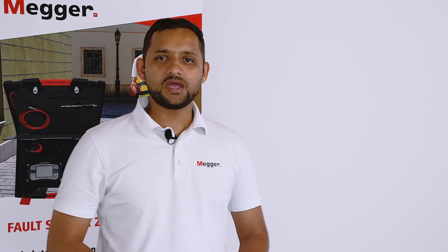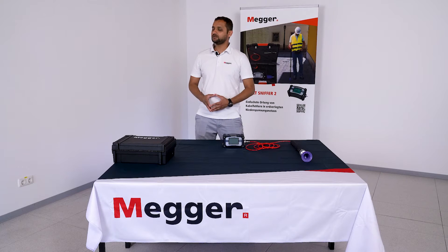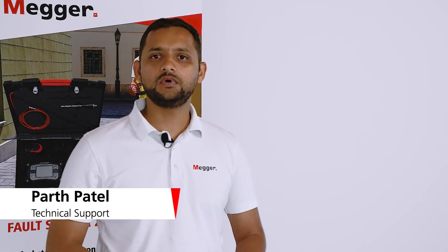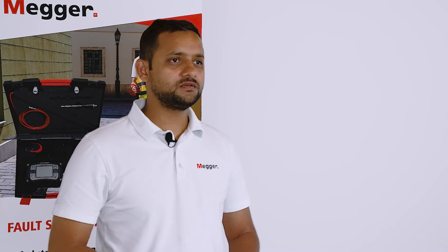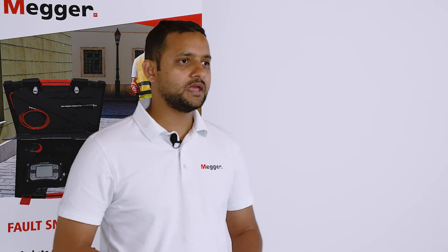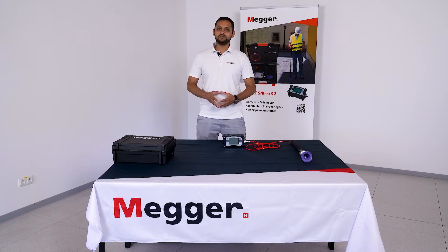The Fault Sniffer 2 by Megger is an innovative tool for finding cable faults in low voltage networks. It does not require disconnecting consumers or removing fuses from houses. The device detects cable faults by measuring gas levels, often caused by burned insulation in T-branch joints. It can also differentiate between natural gases and burned insulation gases.